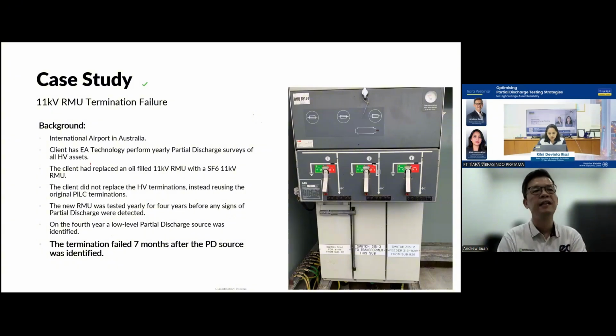And then recently, one year they say, oh, our RMU is very old already. It's an oil filled RMU. So we decided to change to a new RMU, the SF6 RMU. So although they changed the new RMU, unfortunately they did not replace the cable termination. Instead, they used back the old one, the old cable termination from the oil filled RMU. So this was the root cause of the problem.